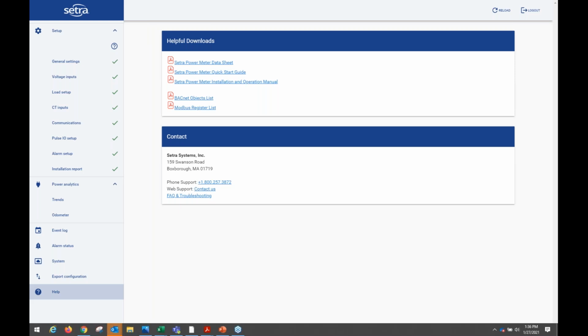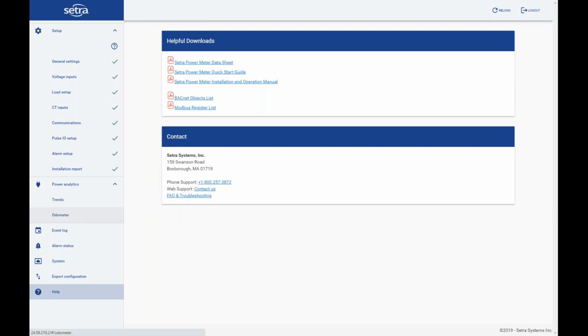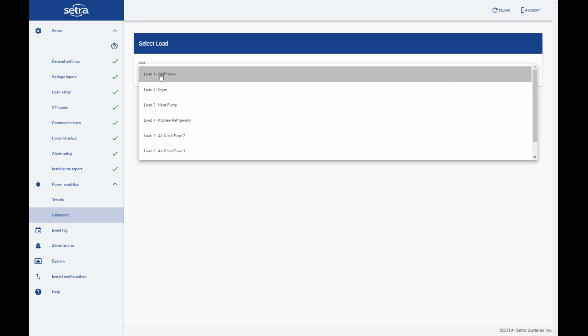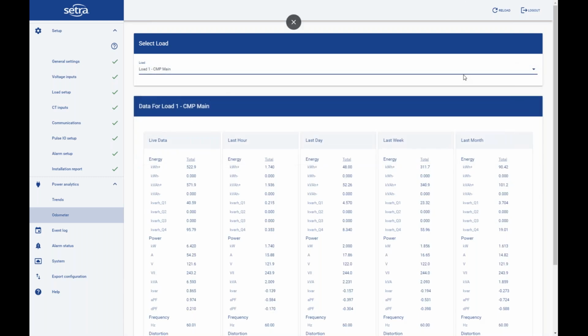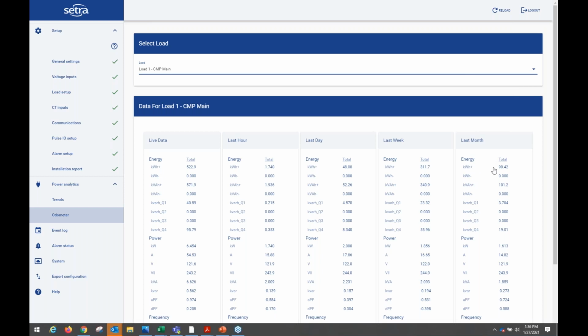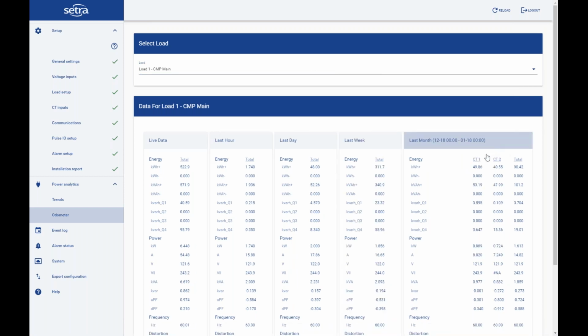And one last question here before we wrap up. Is it possible to get a report for monthly kilowatt usage? Yeah, there's a couple different ways to access that. One is through the odometer. If you picture this load 1 as a building or an apartment, or the total usage within that space that you were going to bill, you can get the kilowatt hours that were used in the last month. In this last month, you can see it's from December 18th to January 18th. And you can set that billing day from 1 to 28 on the general settings page. So if your electric bill is generated on the 15th or the 7th or something like that, it'll bin that last month of data so that you can see that.